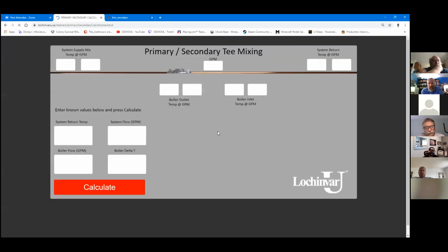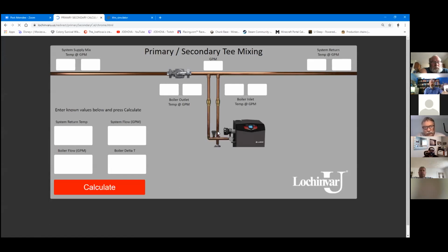One thing too, before we leave calculators, because this is one that I use all the time: when we try to explain primary secondary to people that have never been introduced to it before, their eyes start to glaze over and they start imagining somewhere else they would rather be than in front of me listening to this. A lot of people have a hard time imagining it. And now, since we've gone to a lot of fire tube systems, people are wanting to get away from primary secondary altogether. And keep in mind, Lochinvar did not create primary secondary. That was B&G way back in the day. I think Gil Carlson probably came up with it.